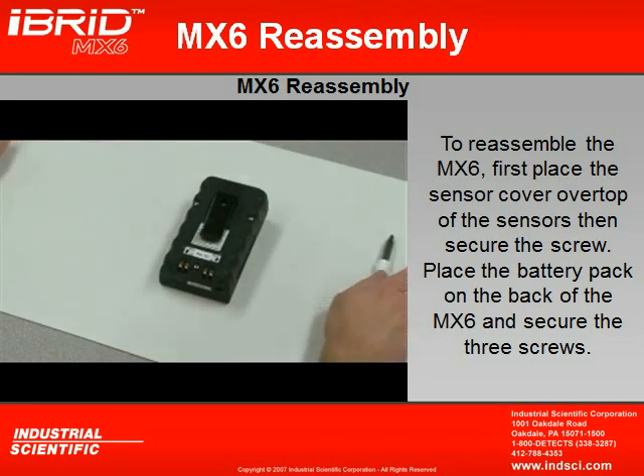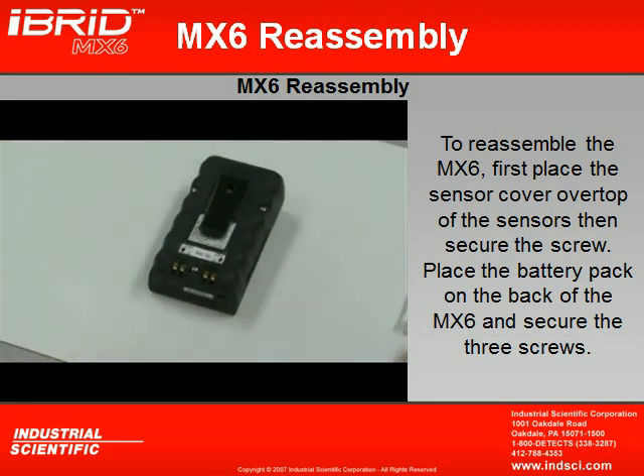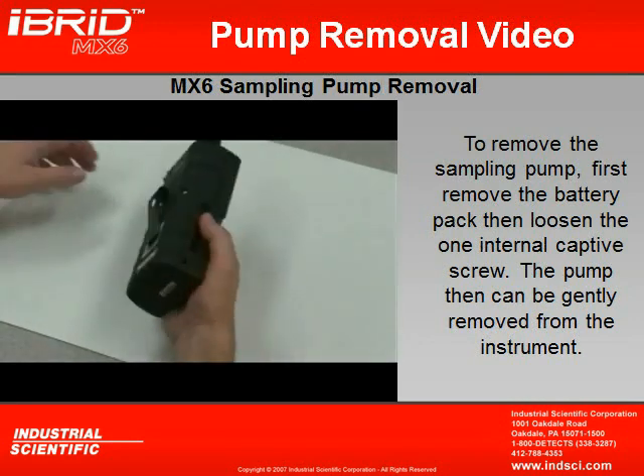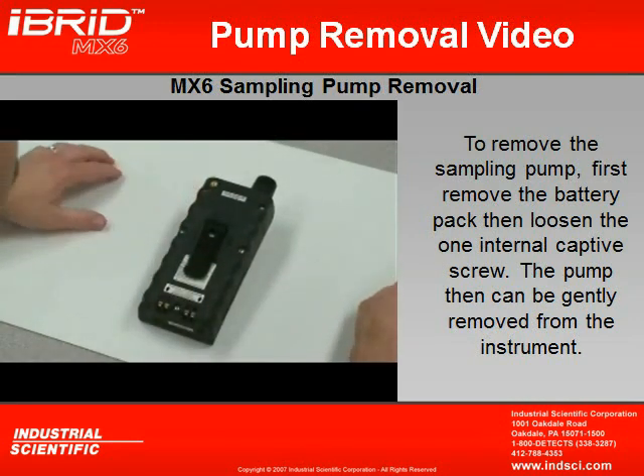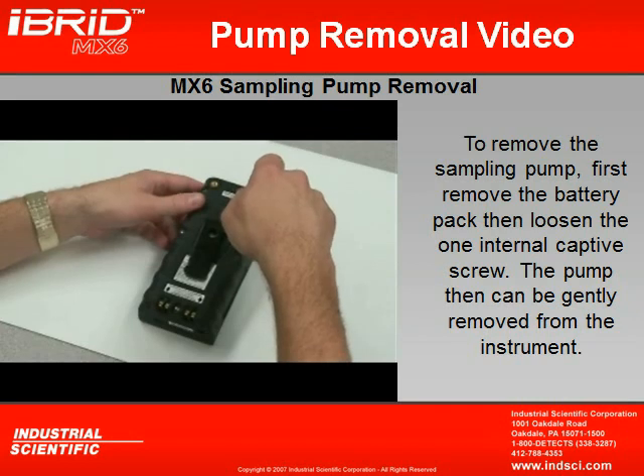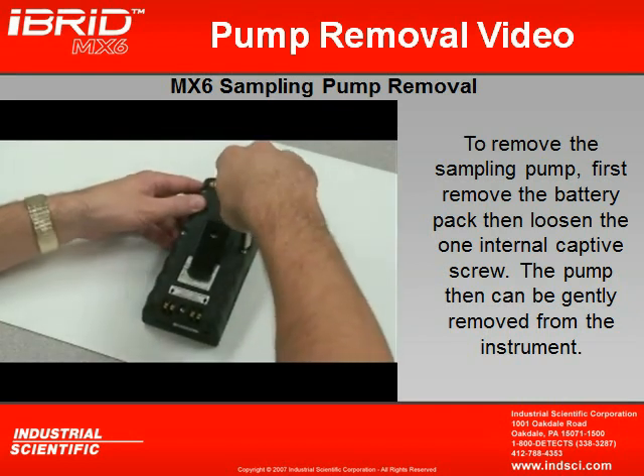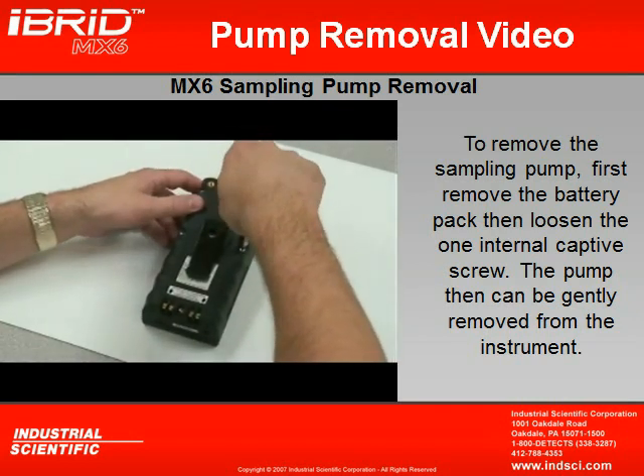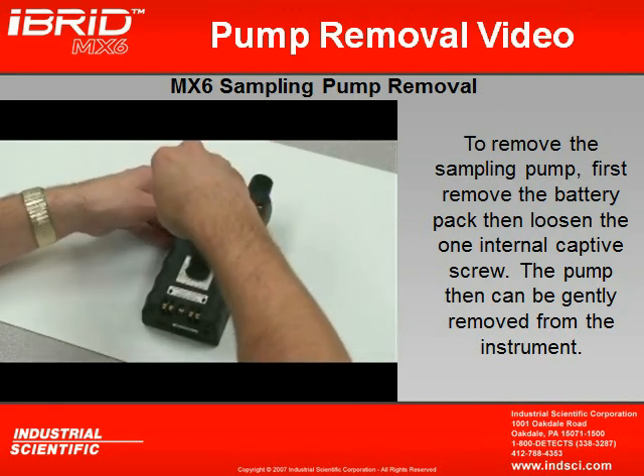Let's look at removing a sampling pump. If I have a sampling pump in my MX6, I can remove that sampling pump to make it a diffusion instrument. The first thing I must do is, of course, fully loosen the 3 captive Phillips head screws on the back of the battery pack.